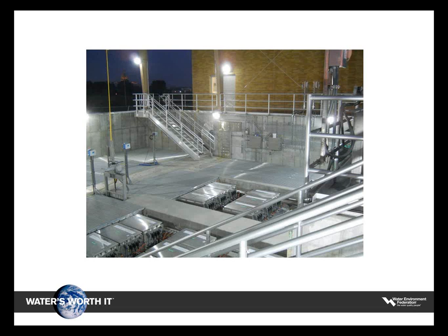All done, everything in. Here you get an idea. You can see we have a module that monitors our transmittance in the back so that we can make sure that it's in the range. Right now we average about 75% of UV transmittance for our facility, and we're very, very pleased. And that is the conclusion of my portion of this talk.